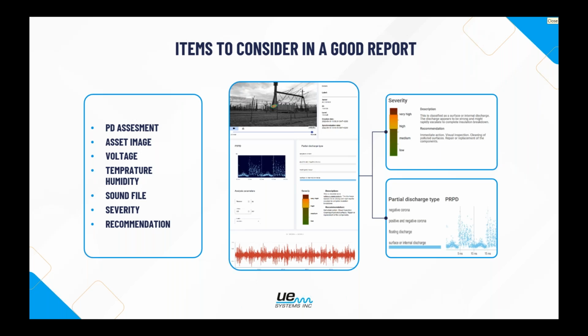If you have the right certification level and understanding of the analysis platform, or in the example of the AI software where it can actually do this for you, I would include the severity. Where the AI software comes in is it includes voltage, distance, and type of equipment, and from there it can make a severity assessment, as you see here on the screen. And then regardless of which platform you use, I would always include a recommendation, whether that's de-energize, further inspect, or infrared inspection because we didn't have that equipment at the time, whatever it might be. I would have some sort of recommendation moving forward.